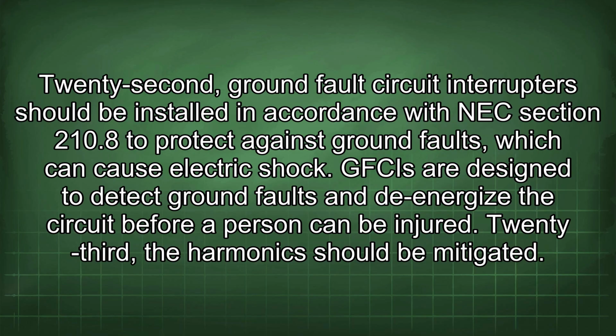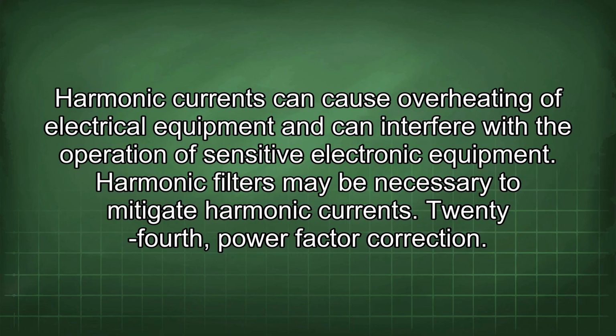22nd, ground fault circuit interrupters should be installed in accordance with NEC section 210.8 to protect against ground faults, which can cause electric shock. GFCIs are designed to detect ground faults and to de-energize the circuit before a person can be injured. 23rd, the harmonics should be mitigated. Harmonic currents can cause overheating of electrical equipment and can interfere with the operation of sensitive electronic equipment. Harmonic filters may be necessary to mitigate harmonic currents.